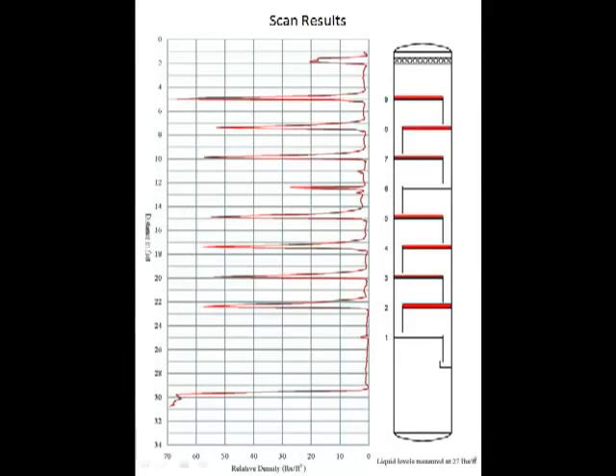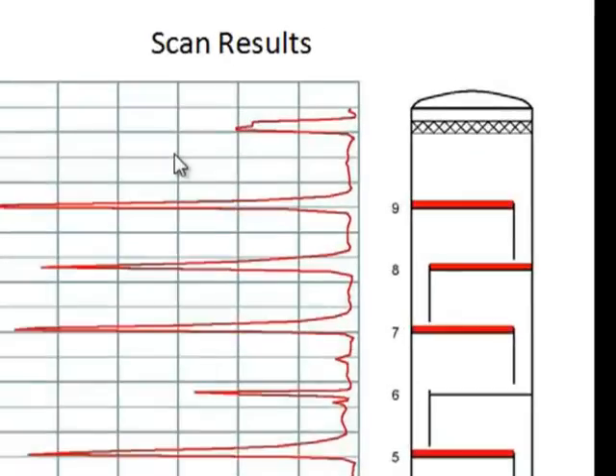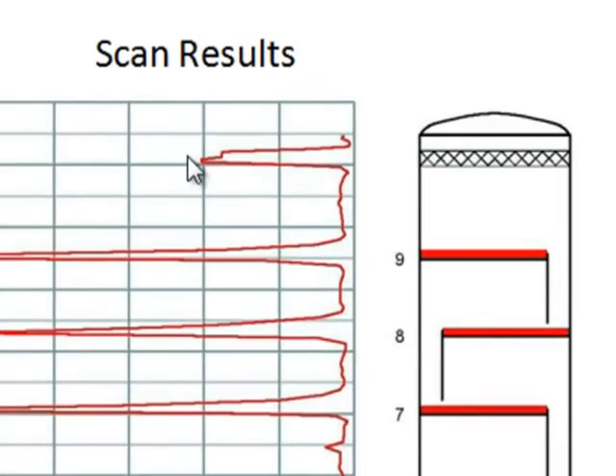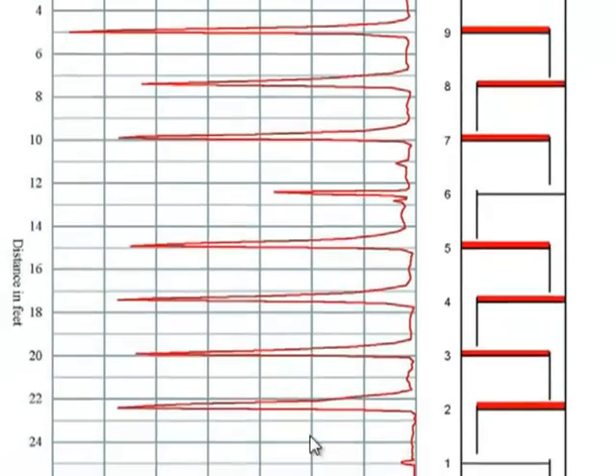This is a density plot showing the results of the gamma scan. Low density on the right-hand side of the plot increases in density to the left. Absorptions can be seen for a mist eliminator in the top of the tower and for most of the trays.